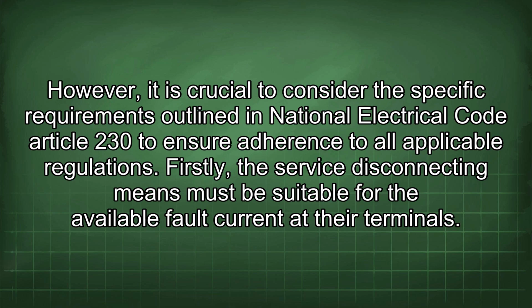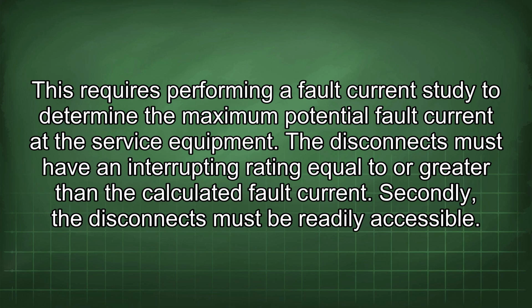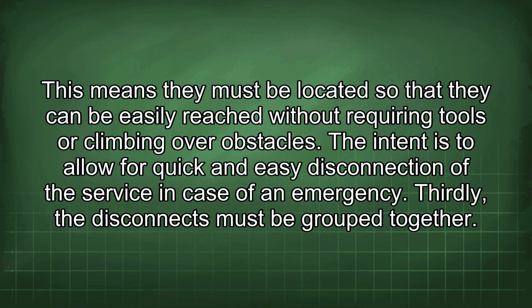Firstly, the service disconnecting means must be suitable for the available fault current at their terminals. This requires performing a fault current study to determine the maximum potential fault current at the service equipment. The disconnects must have an interrupting rating equal to or greater than the calculated fault current. Secondly, the disconnects must be readily accessible. This means they must be located so that they can be easily reached without requiring tools or climbing over obstacles. The intent is to allow for quick and easy disconnection of the service in case of an emergency.